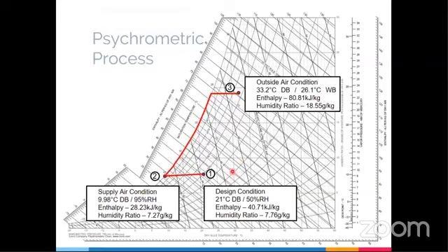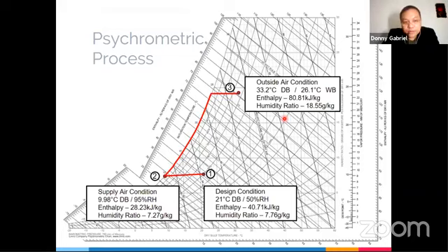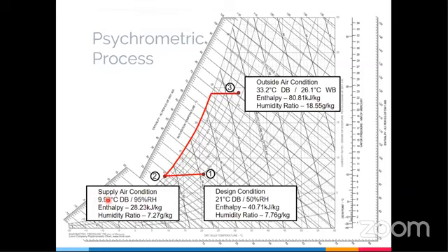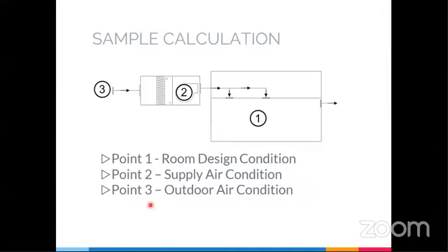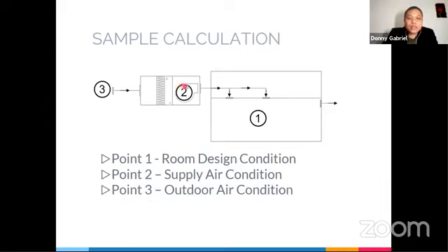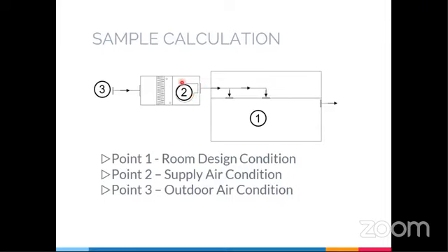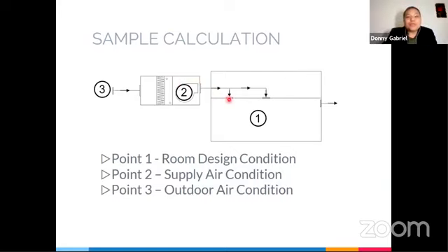Hi, Sir Danny. Yes. Where did you get the 9.98 degrees Celsius? Which one? This one? Yeah. Is it from the cooling coil? Okay. Or it's already distributed to the duct? Going back. The condition after the cooling coil, here the AHU and the ducting are considered insulated. So whatever condition after the cooling coil will be the same condition before it comes out to your room.